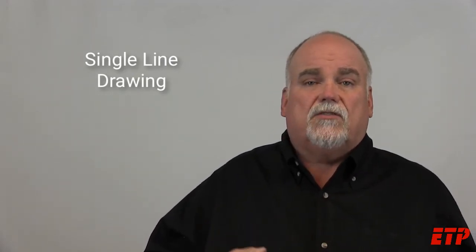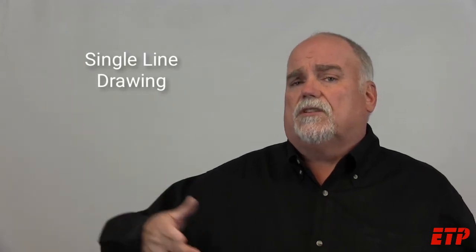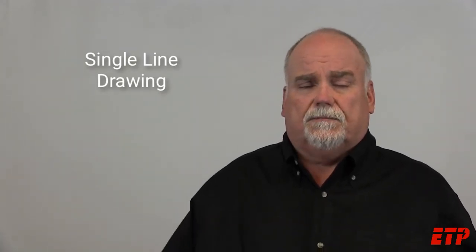This data collection includes starting at your utility connections where your service entrances are, and tracing wires, conductors, cabinets, fuses, circuit breakers, all the way down to your utilization equipment on the factory floor or your facility floor. So we're going to trace all those wires: what's connected to what, what cabinet goes to what cabinet, what circuit breaker connects what piece of equipment, and protects what conductors.